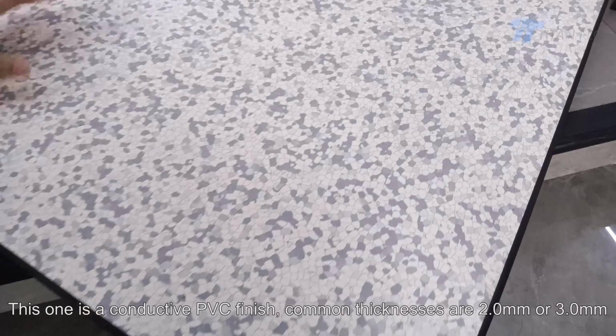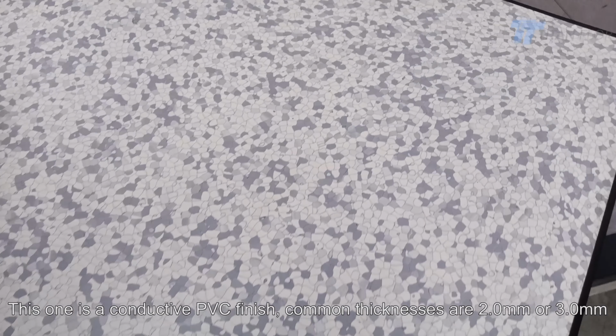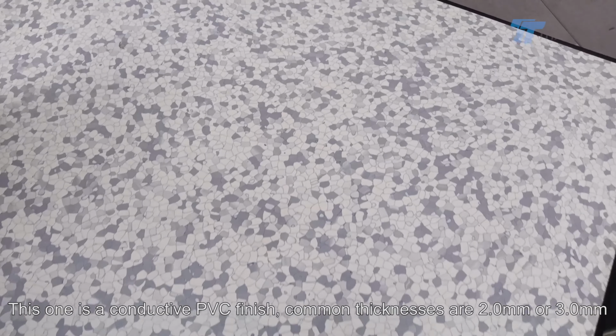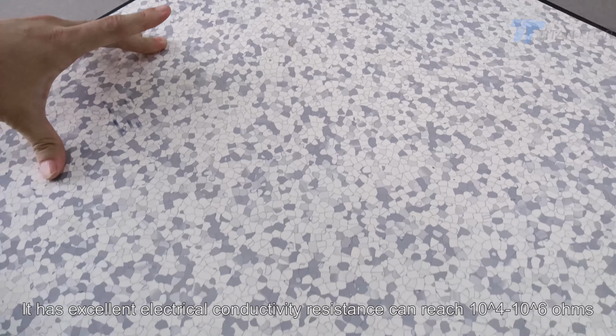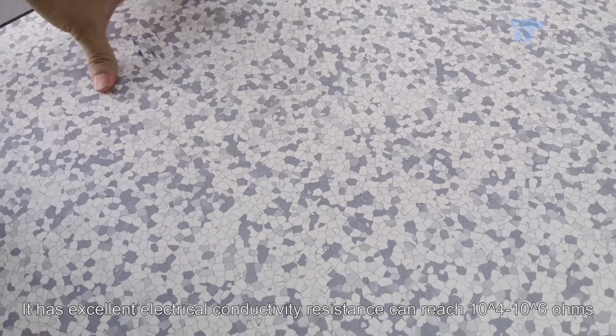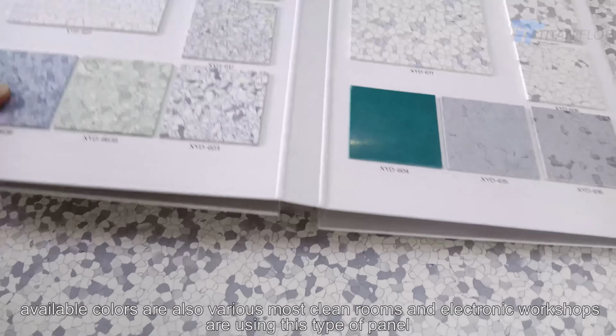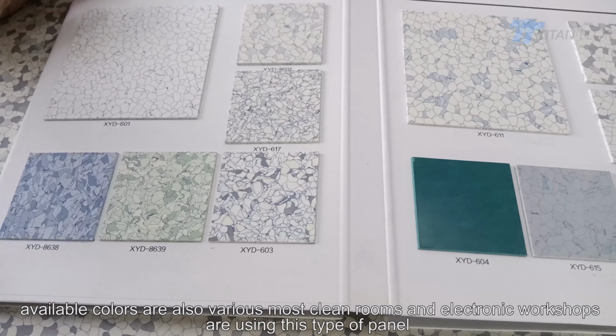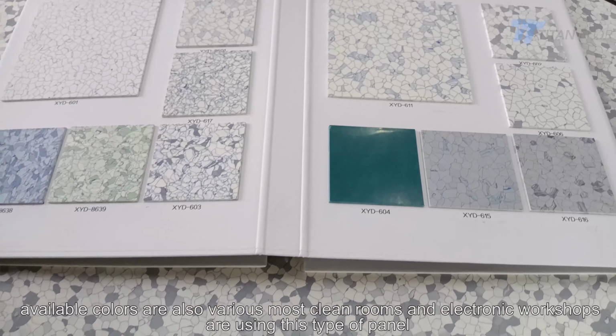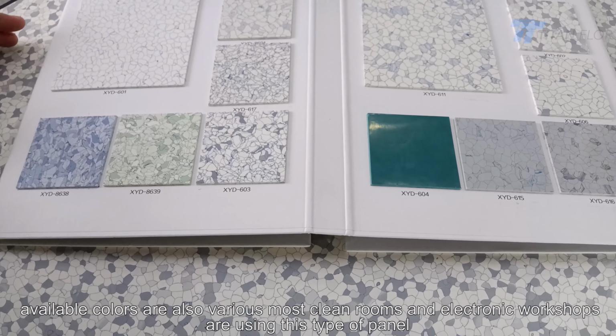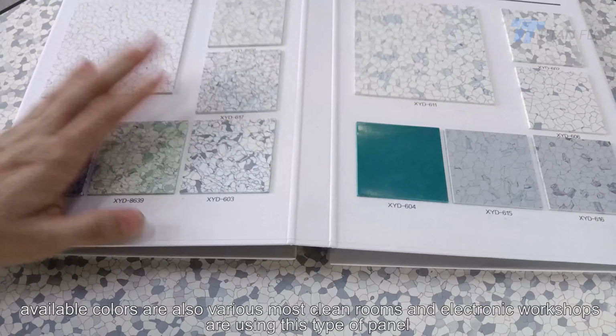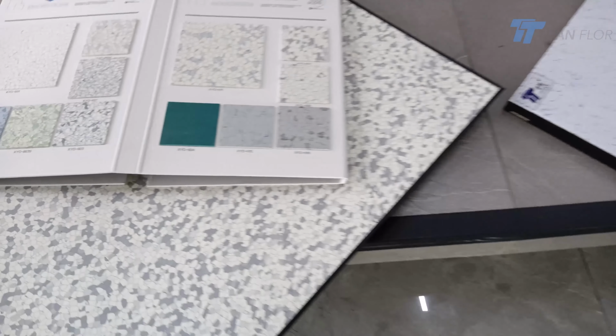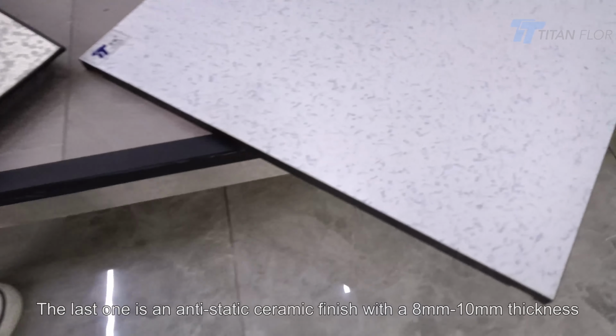This one is a conductive PVC finish. Common thicknesses are 2 or 3 mm. It has excellent electrical conductivity. Resistance can reach 10^4 to 10^6 ohms. Available colors are also various. Most clean rooms and electronic workshops are using this type of panel.